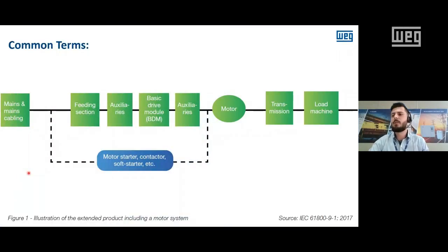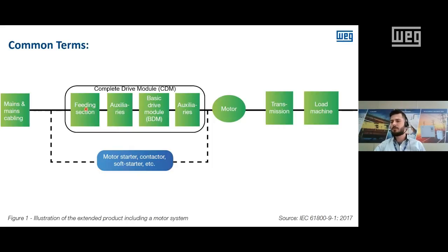Okay, so let's talk about some common terms. We have here a complete system, from the mains and the main cabling all the way through to the load machine, and we have a lot of parts here. If you see right in the middle, we have the complete drive module. The complete drive module comprises the feeding section, the auxiliary parts that sometimes are here, and the basic drive module, the BDM, and sometimes some auxiliary systems at the end. So basically here we have the most common rectifier unit at the input, and then we have the IGBT part, the inverter unit here. This is what we call the complete drive module.